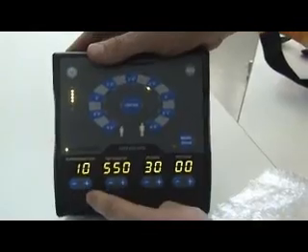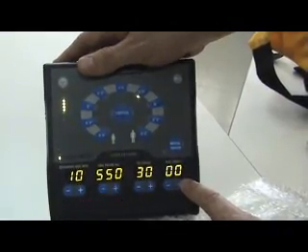All of these values displayed are the respiratory rate, the tidal volume, the PIP or peak inspiratory pressures, and the PEEP or positive end-expiratory pressure — for difficult-to-oxygenate patients and those with ARDS. Here is the air intake, the exhalation port, the supplemental oxygen port, and one of the sensors that tells you what's going on with the patient's CO2 and oxygen levels. It's also got connections so that you can remotely send information — a USB driver — and later the unit will be equipped with GPS to send information to a physician so that lesser-trained people can run the ventilated patient while a physician remotely alters the settings.